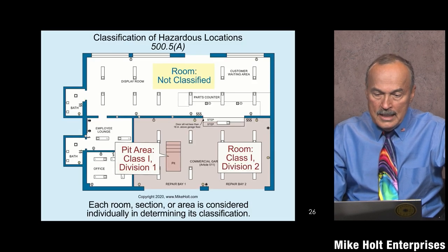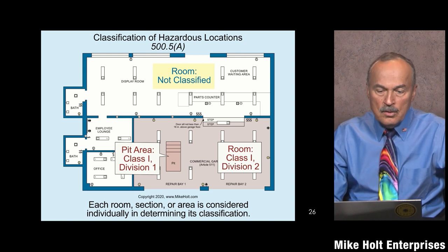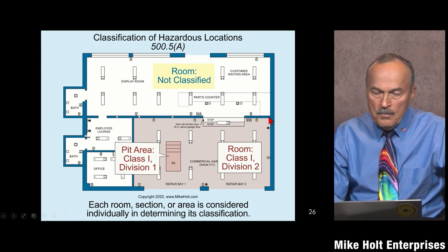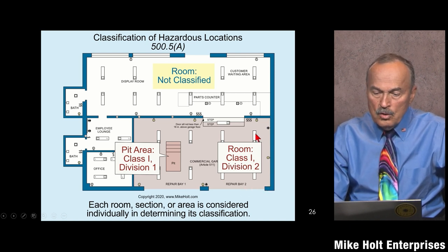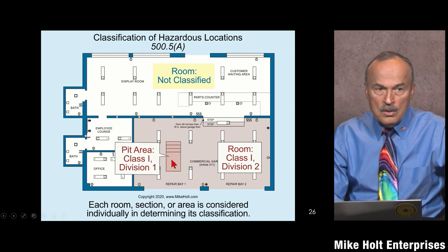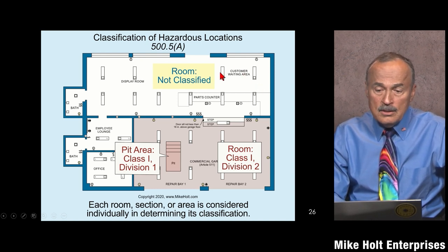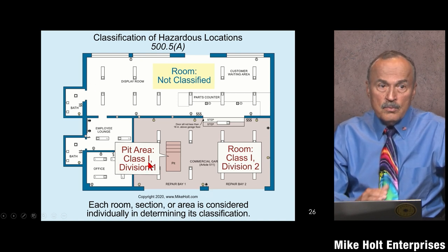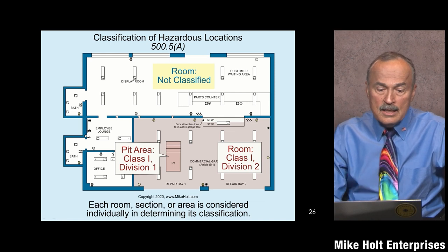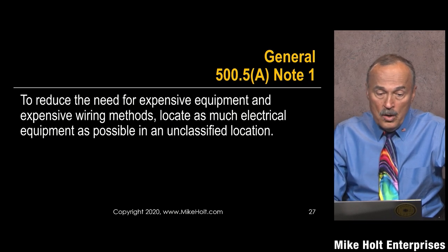Each room or area is considered individually in determining its classification. For example, somebody has determined that this area here is a Class 1 Division 2, and the pit is a Class 1 Division 1. All the other spots not classified are just Chapter 1 through 4 wiring, but once you're in a classified location you have to comply with Chapter 5 — specifically Article 501.